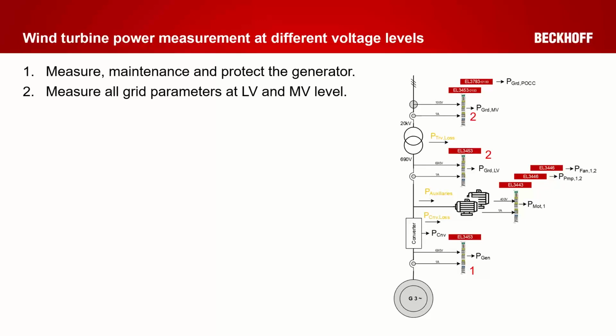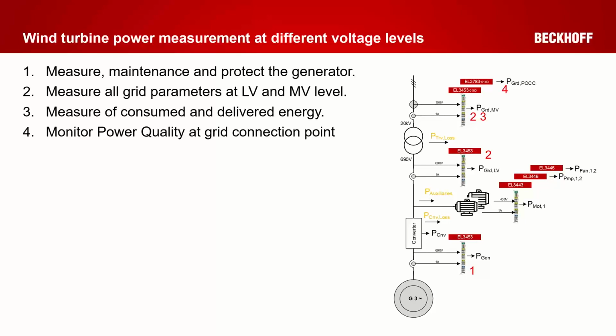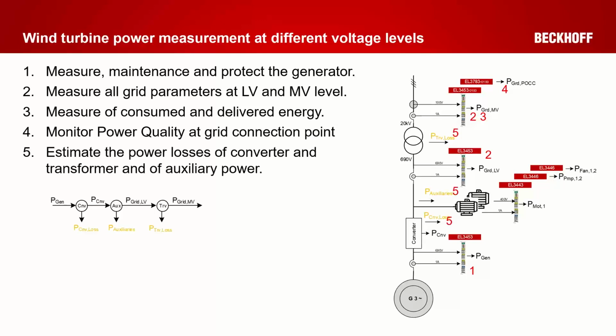Second, we are maybe interested in the main connection point at the low voltage and medium voltage level, the power, and our grid parameters, mainly on the medium voltage side. And we are interested in the consumed and the delivered energy, which might also be our gain, and also the power quality at the grid connection point. For this, we can use, instead of the EL3453, also the EL3783, which allows you to measure also the instantaneous values for grid fault analysis. Last but not least, using all these powers at the different measuring points, you are now able to estimate the power losses of converter, transformer, and of the auxiliary power.